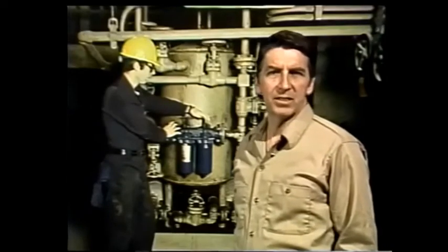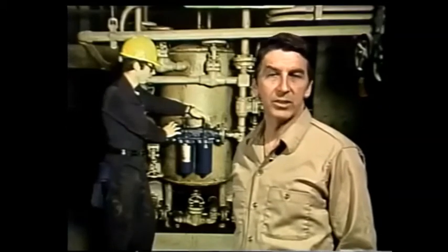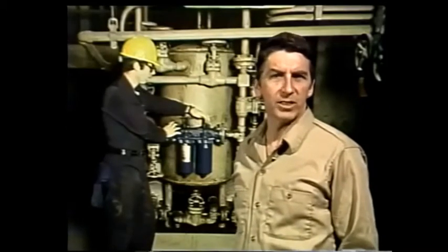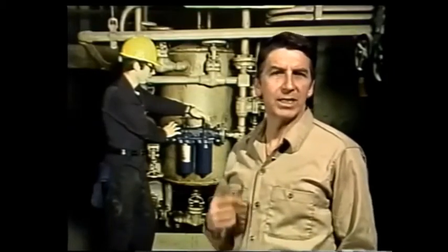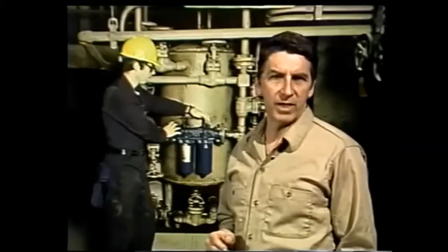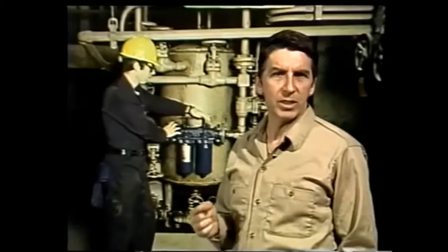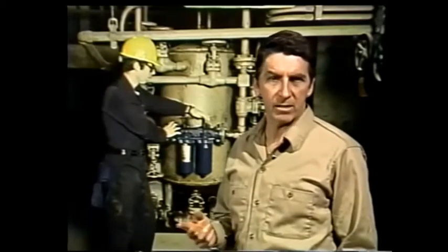One of the obvious advantages of knife edge filters is that they can be cleaned while the system is in operation, while fluid is flowing through them. Now, this makes them ideal for systems which are in constant operation and should not be shut down. They're often found in low-flow, medium to low temperature systems, and they may filter oil, air, or water.